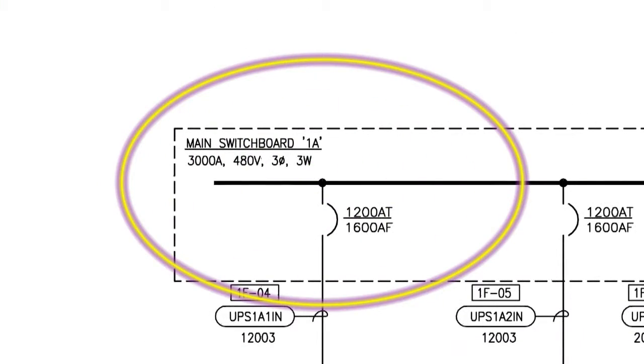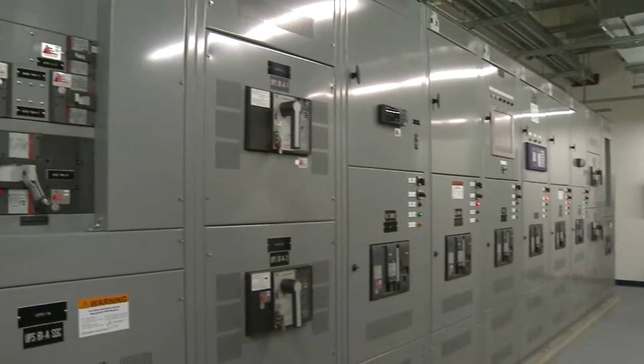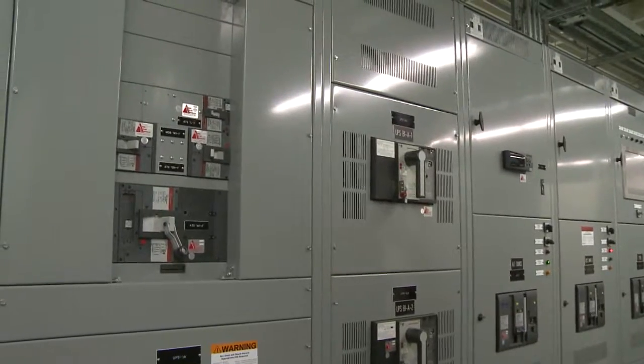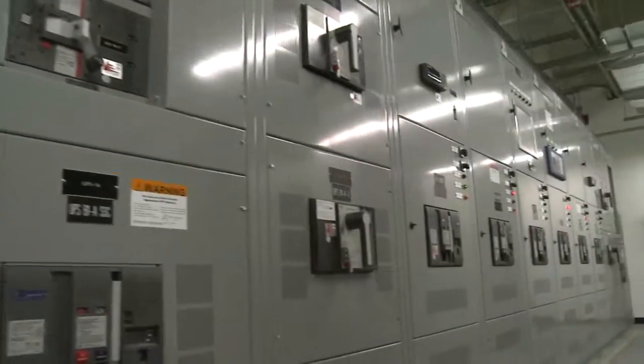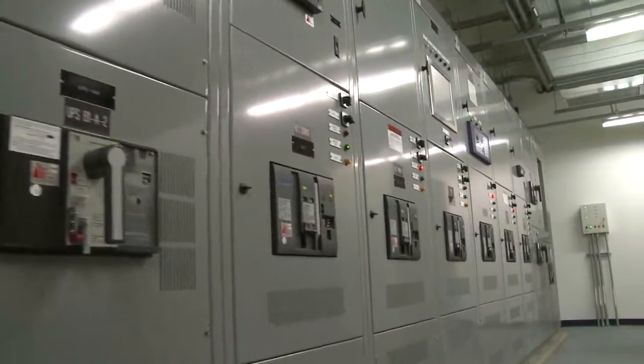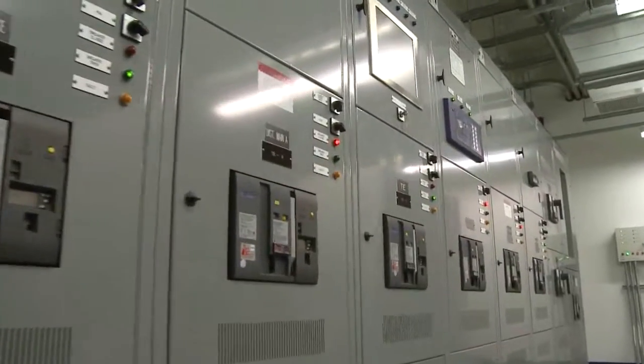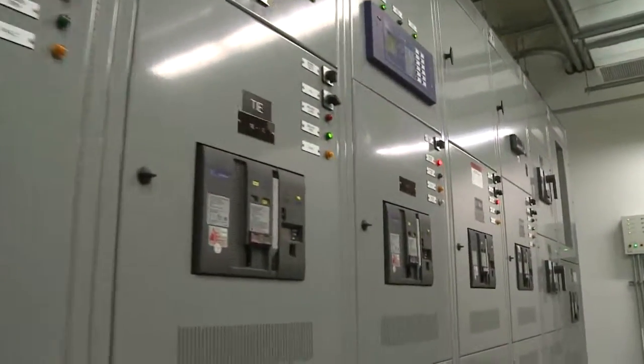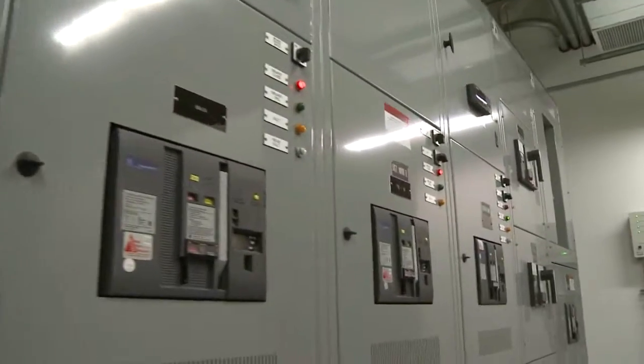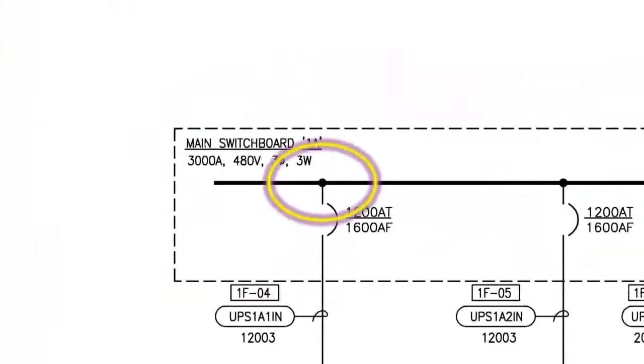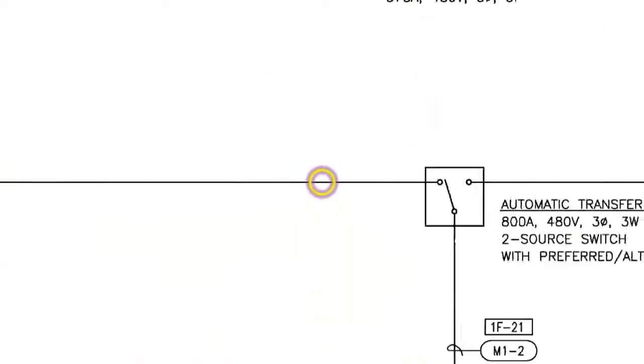The main switchboards are the central location where power is received and distributed to the critical or essential loads. Located on this board are the utility input breakers, diesel generator input breaker, swing generator input breaker, numerous UPS output breakers, and essential loads like cooling and lighting.